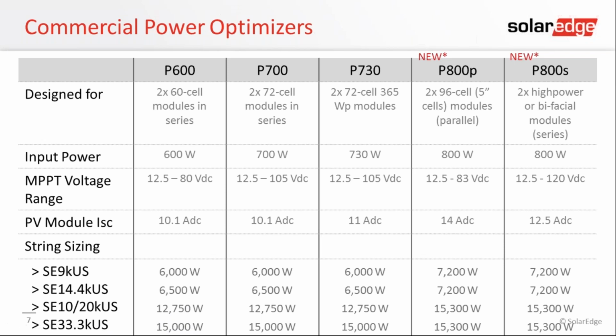Now, some of you may be asking, how do you meet rapid shutdown? If we have 50 modules on 1 string, our modules are installed 2 modules to 1 optimizer. SolarEdge's optimizers, which we'll cover later, have a functionality called SafeDC, and basically in an open circuit voltage state, we revert to 1 volt DC per optimizer. So in a rapid shutdown state with 50 modules on a string, your rooftop voltage would be the number of optimizers you have in series, so 25 optimizers for 25 volts. That's how we meet our rapid shutdown requirements. And if you're using our new P800P and P800S optimizers, that goes up to 15,300 watts per string.